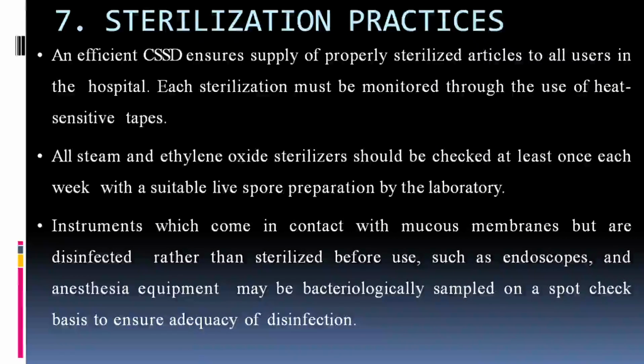Seventh is sterilization practices. An efficient CSSD ensures supply of properly sterilized articles to the hospital. Each sterilization must be monitored through the use of heat-sensitive tapes. All steam and ethylene oxide sterilizers should be checked at least once each week with suitable live spore preparation by the laboratory. Instruments which come in contact with mucous membrane but are disinfected rather than sterilized before use, such as endoscopes and anesthesia equipment, may be bacteriologically sampled on a spot check basis to ensure adequacy of disinfection.